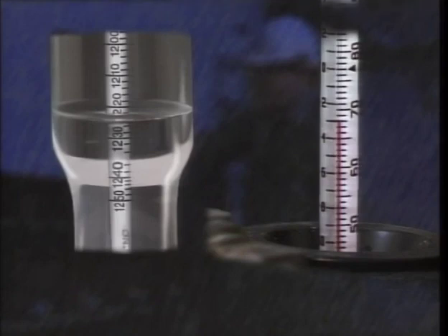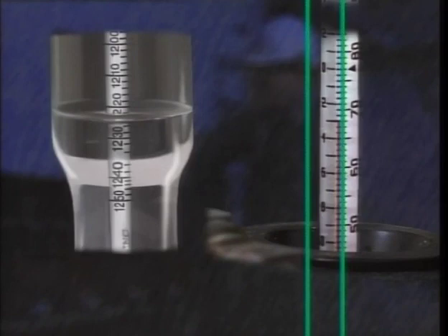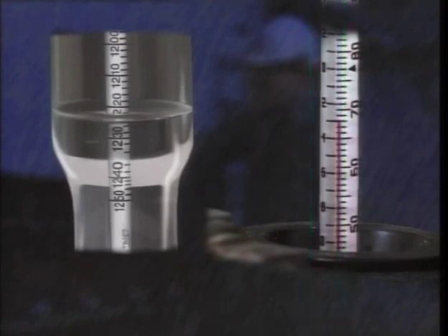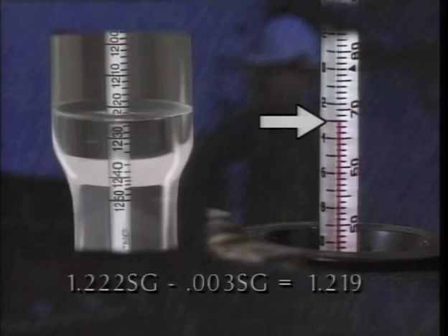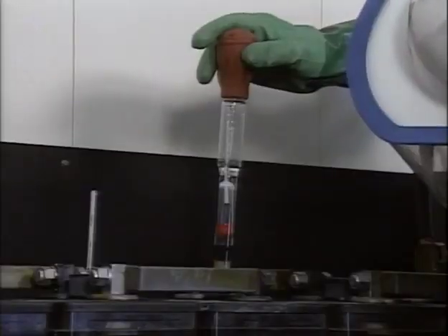Some cell thermometers have a specific gravity correction scale opposite the temperature scale. The correction scale here is marked in thousandths. In this example, the electrolyte temperature is 68 degrees Fahrenheit. The correction factor for this temperature is about -3. So 0.003 is subtracted from the specific gravity reading of 1.222 for a corrected specific gravity of 1.219. This is the value that is recorded for the cell.